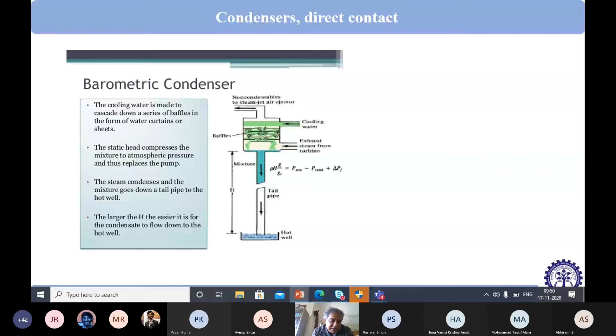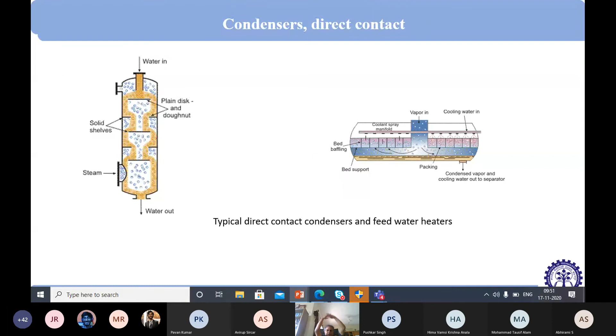Then these are some of the other designs where steam and water come in direct contact and this kind of condensation takes place. These are typically feed water heaters and deaerators, etc. They are made of this kind of design. Here also you see steam is moving in the upward direction, and there are plates, baffles, etc. to create obstacles, and water is falling from the top, so that water and steam make some sort of intense contact. Here also this counter current kind of flow has been provided. So this gives us some idea regarding how direct contact condensers will work for steam and water.